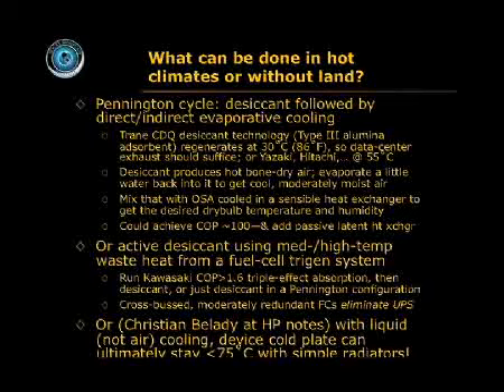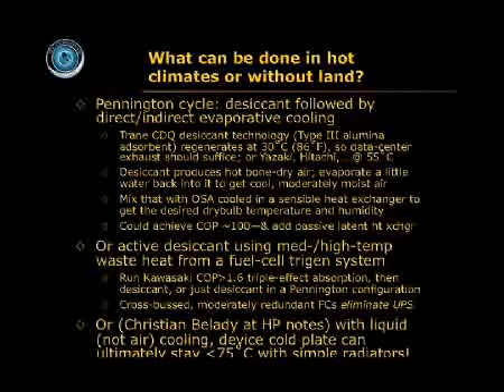Oh, by the way, we can use another trick called a passive latent heat exchanger. Here's how it works. Take your 100% outside air building, and as the air comes in, pre-chill it. I'll tell you how in a minute. Take the condensate that drops out of it, run it preferably by gravity to where you're exhausting air from the building, evaporate it into the exhaust air, thereby evaporatively cooling the exhaust air more or less to wet bulb ambient, capture the sensible cool with a heat exchanger, and bring that sensible cool back passively in a heat pipe to where you started, and that's how you pre-chill the outside air. In other words, you recover the dryness that you paid to create in the air you're exhausting, and the only moving part is the working fluid.